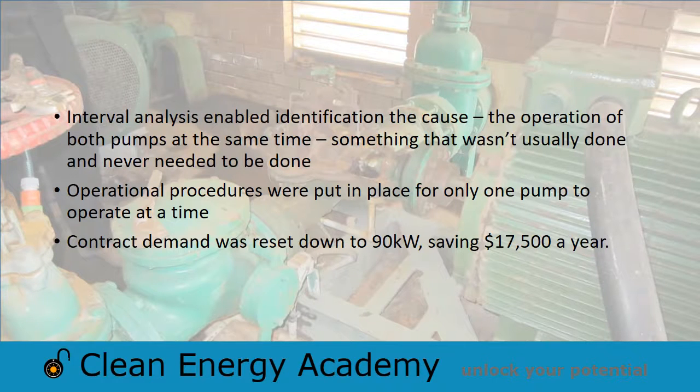As a result, operational procedures were put in place for only one pump to operate at a time. The contract demand was reset down to 90 kilowatts, saving $17,500 a year.